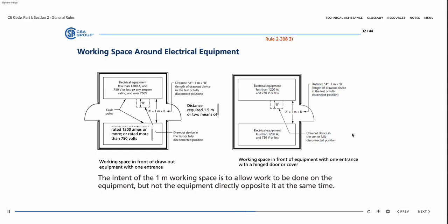The working space of 1 meter around electrical equipment with a rating of less than 1200 amperes and operating on a 750 volt or less system, as shown in the figure, is to allow the enclosure doors or hinged panels to open a minimum of 90 degrees.